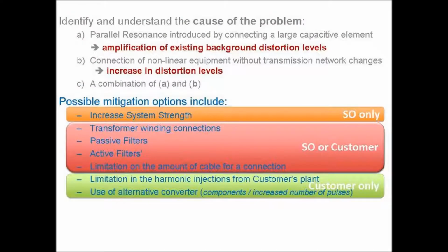So harmonic mitigation options. We've already talked a little bit about resonances. Basically, if you've got a resonance, that's part of the cause of the problem. If you've got injected currents onto the system, that's another bad thing in terms of problems. So if you've got resonance and currents coming together, that's probably a worst case scenario. So that's scenario C there, where you've got a combination of new distortion and amplification from the change in resonance.